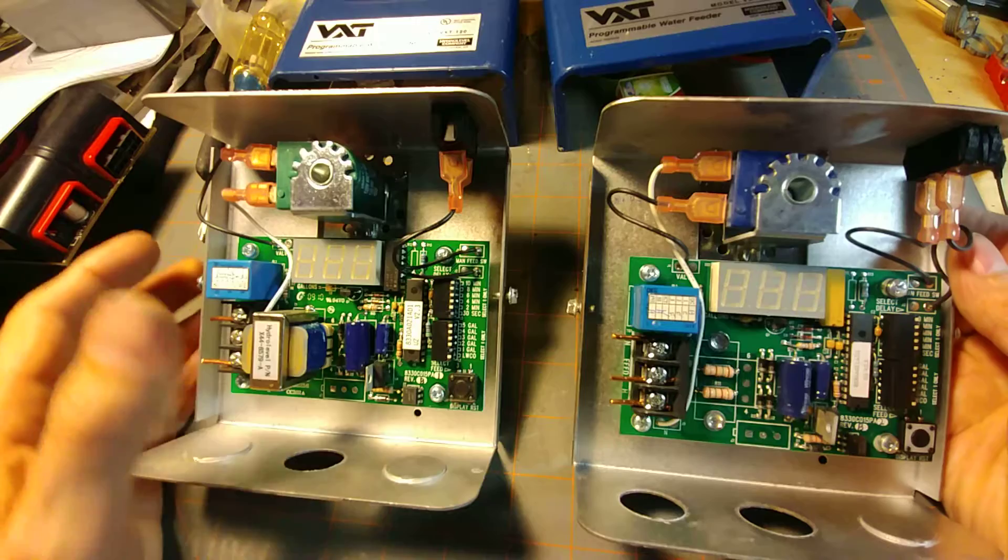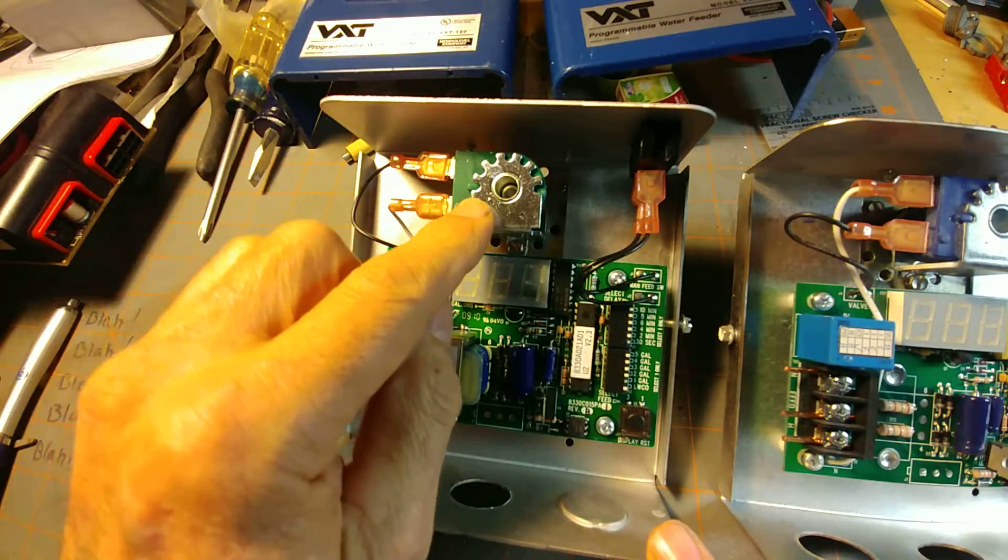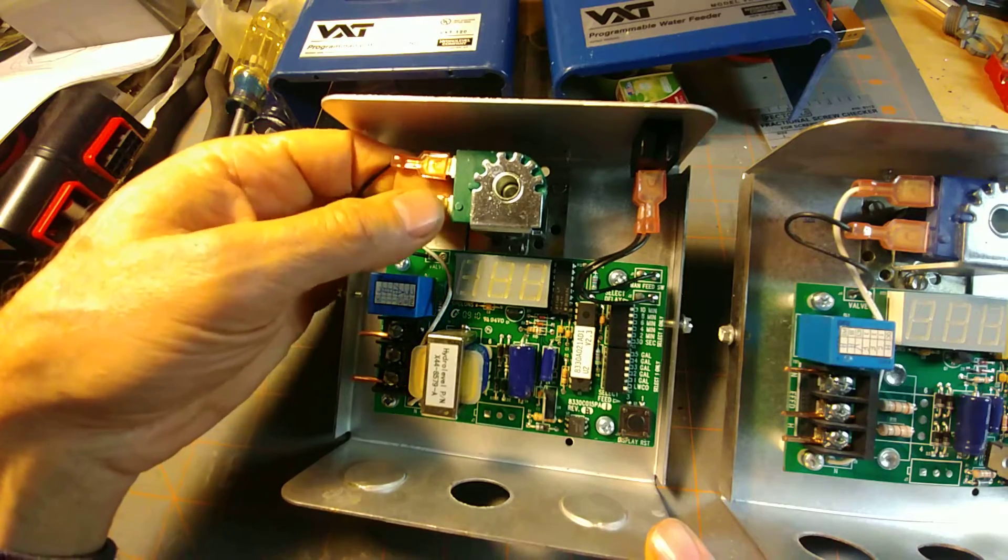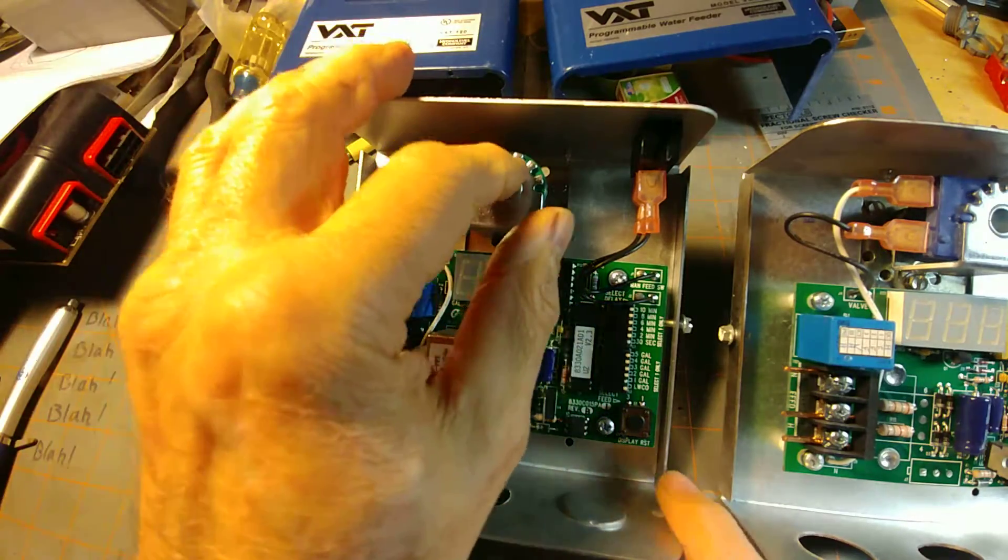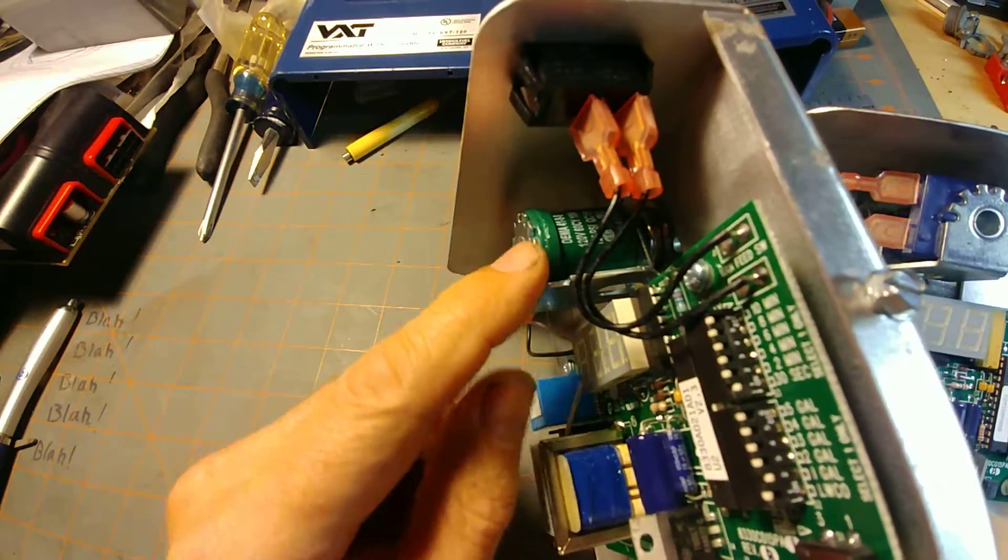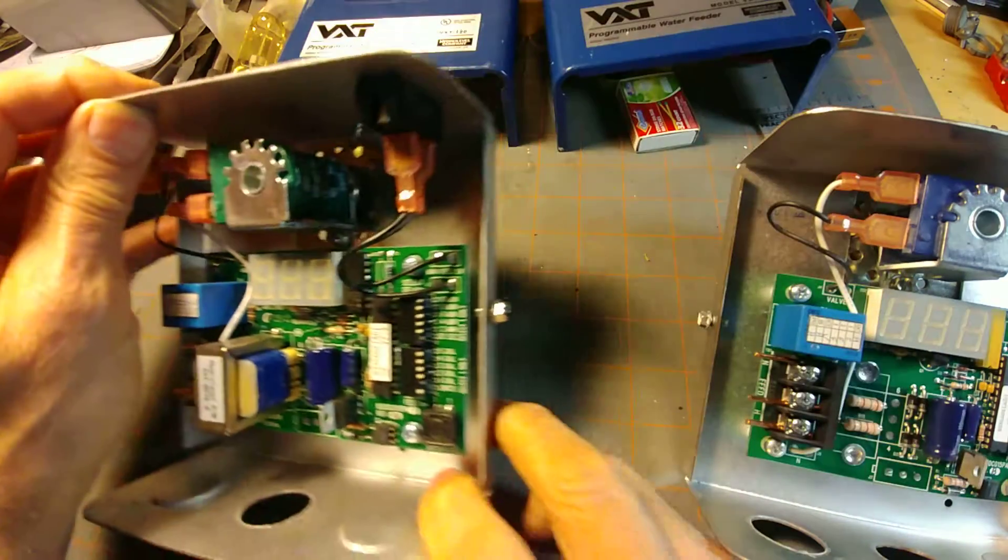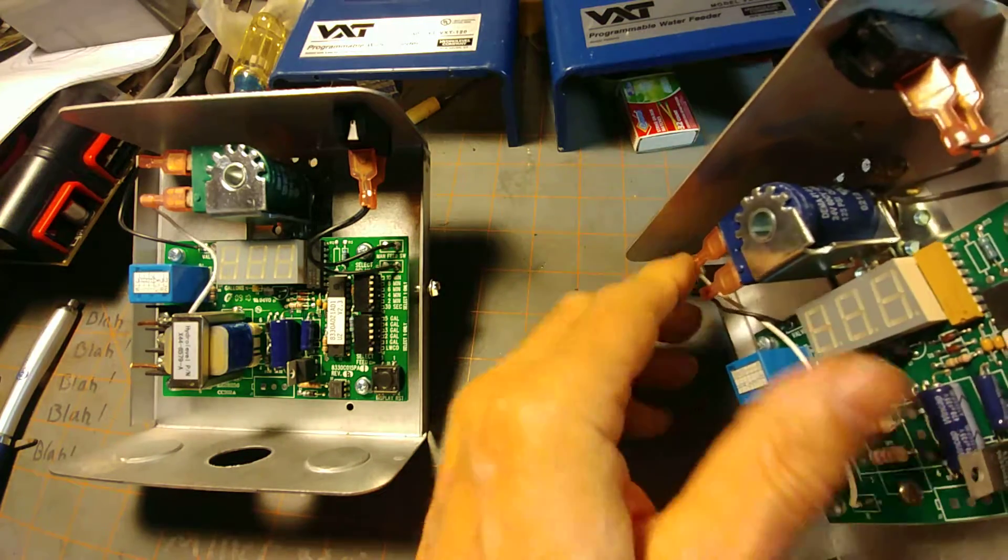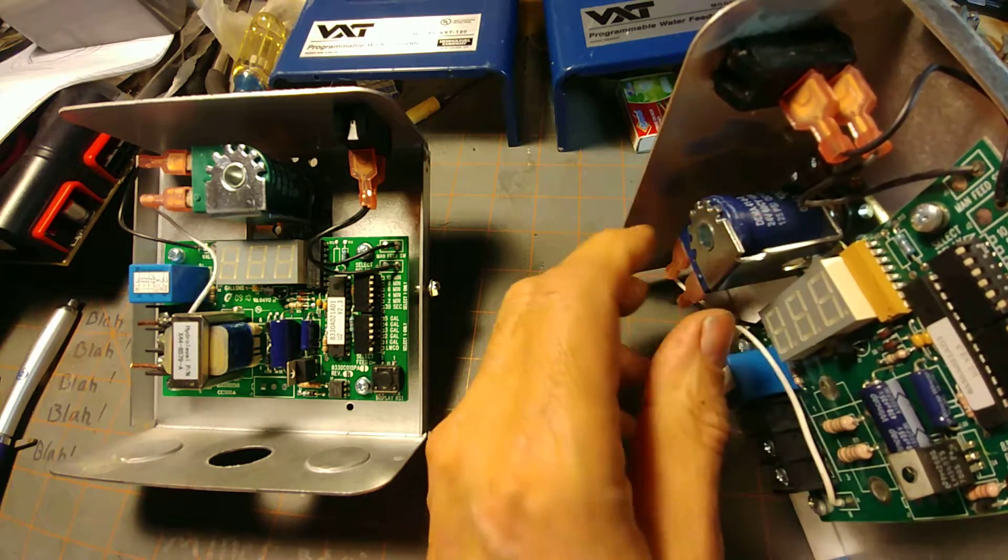The other difference is the solenoid coil. When this is energized, you've got 120 volts here going into this coil, which is 120 volts and coated green. And 24 volts goes into here, and it's coated blue.